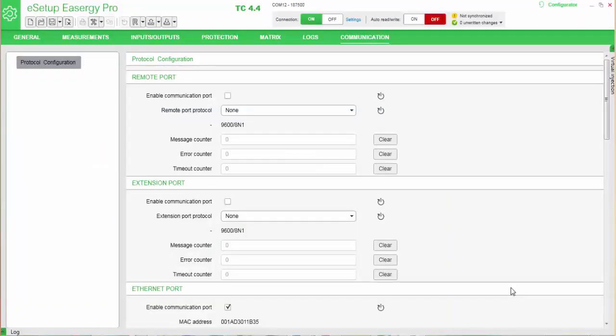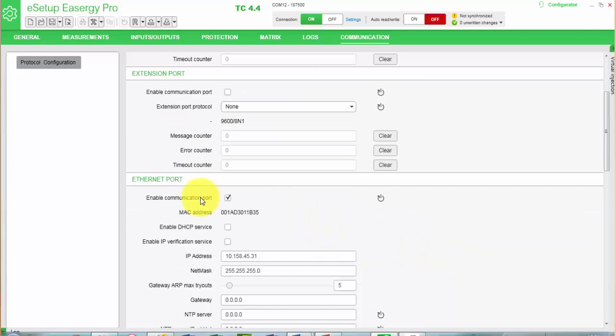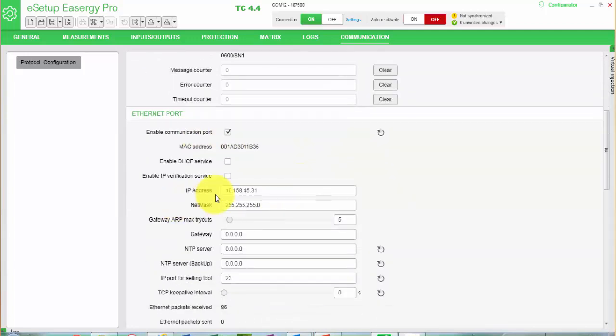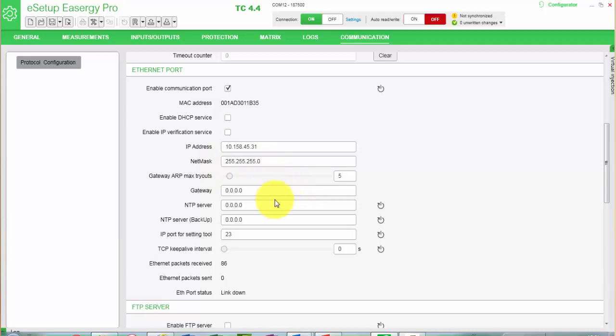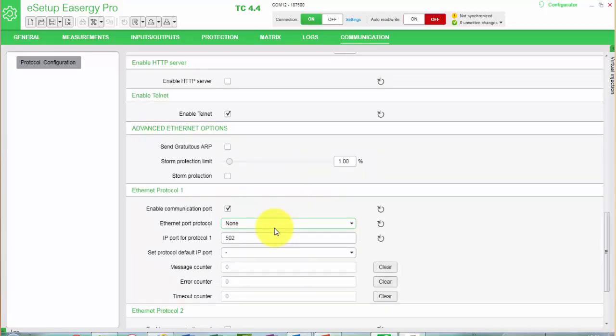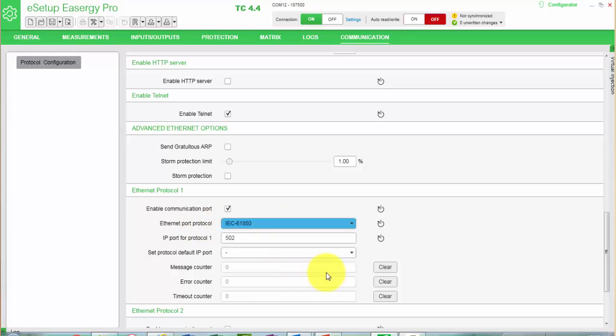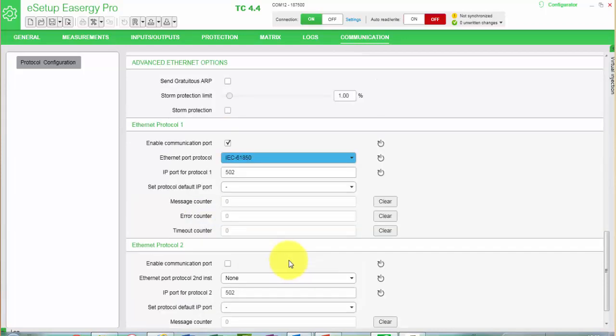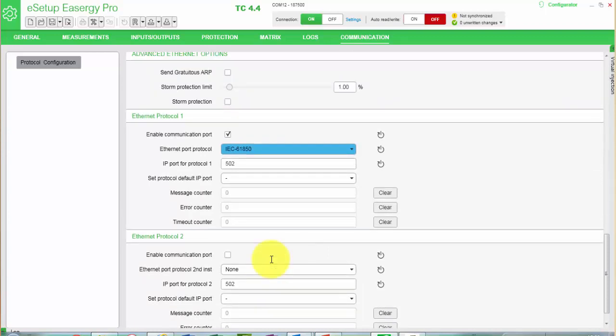So the first step, I will go to the protocol configuration menu. I will select the protocol configuration. I will enable the communication port for Ethernet port, I will add the IP address, I will put the netmask, and if we would need to use a gateway or NTP server, I will add this address. Then I will go to the Ethernet protocol number 1, I will define IEC 61850. All the other parameters in this menu we can leave as they are, we only need to modify them in special occasions.